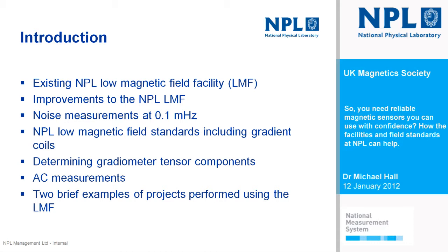I'll look at NPL low magnetic field standards, which includes gradient coils. That's a new field standard that we've recently added. I'll explain why that was needed and how we have calibrated, and how that coil system is then used to calibrate the customer ESA's gradiometer. Look at the tensor components, and then I'll move on to AC measurements, what capabilities we have, and how we calibrate the coils that are used to perform the calibration, also in the low magnetic field lab, of AC sensors. And I'll give a couple of brief examples of projects which have been performed using the facilities that I've covered in the low magnetic field lab.